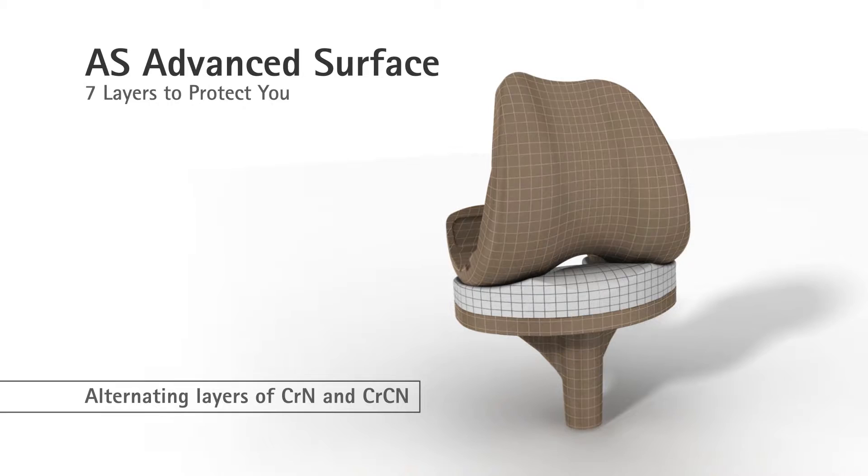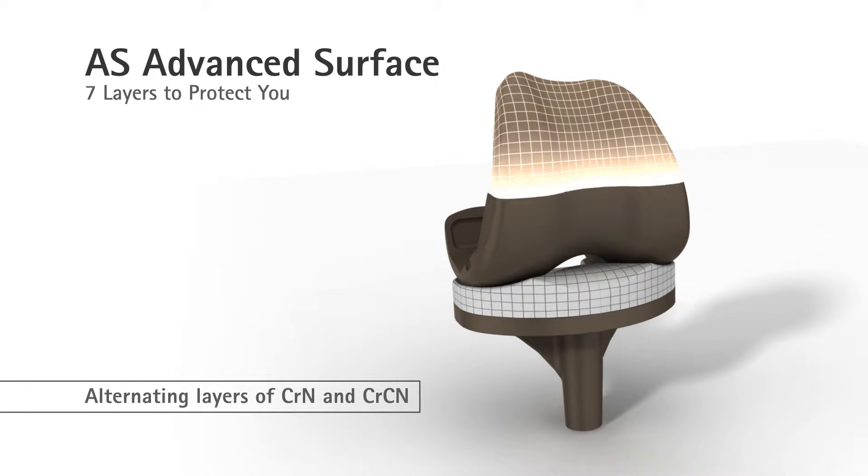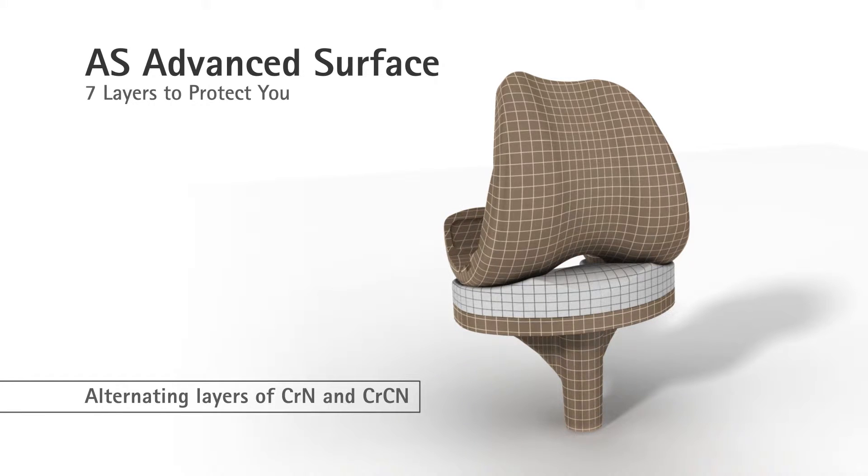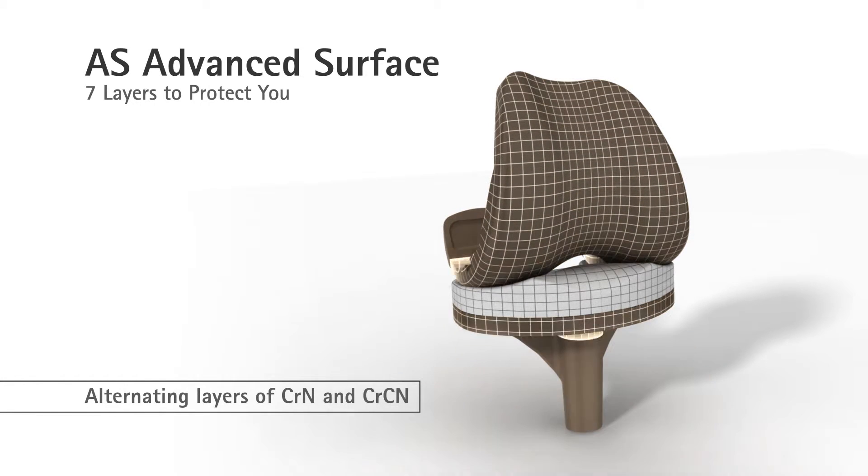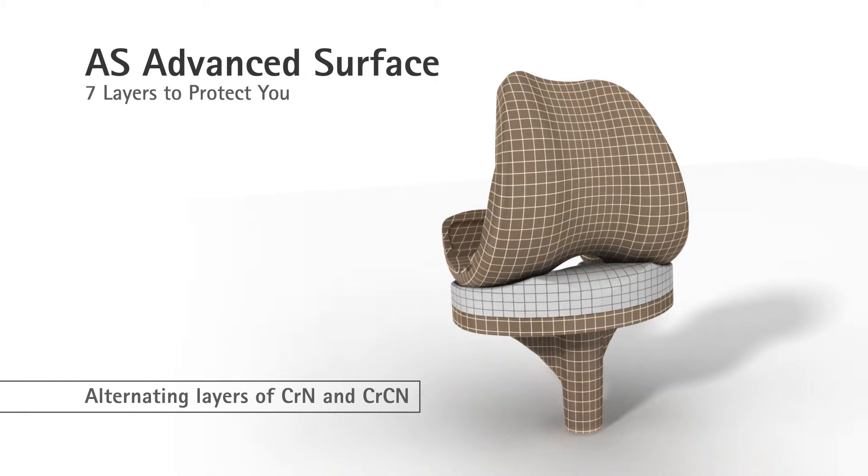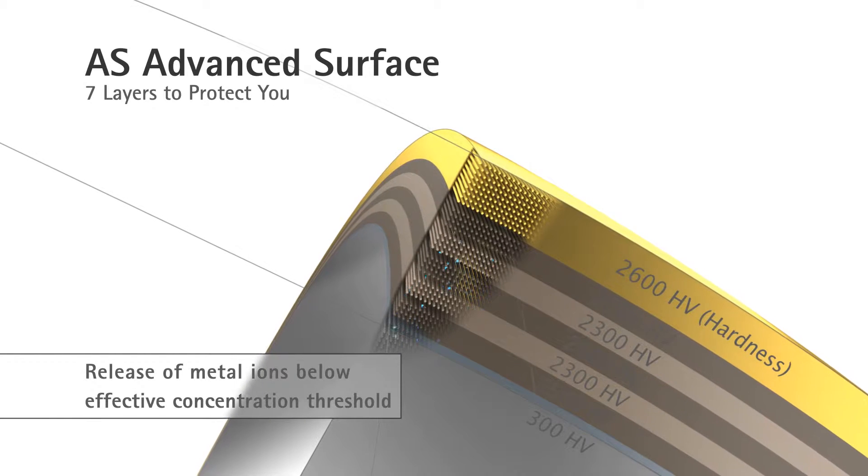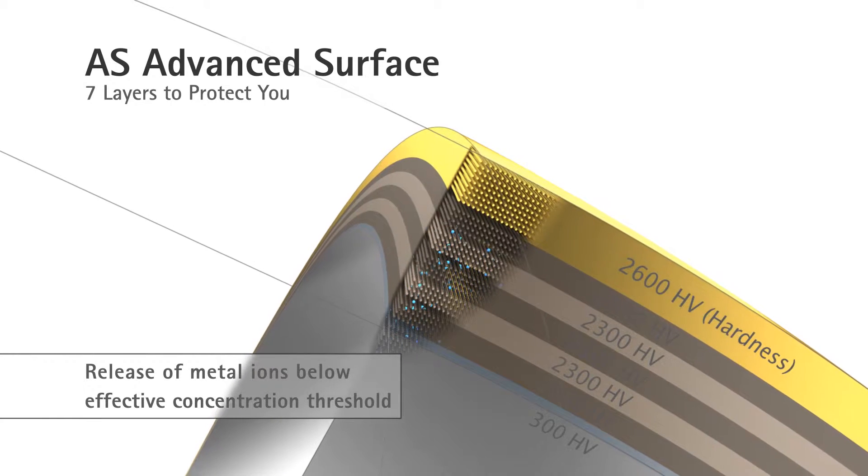The five transition layers provide a reliable barrier that prevents the release of metal ions, effectively reducing the allergenic potential of the implant. In laboratory tests, the concentration of metal ions in the advanced surface coating was found to be below the effective concentration threshold.